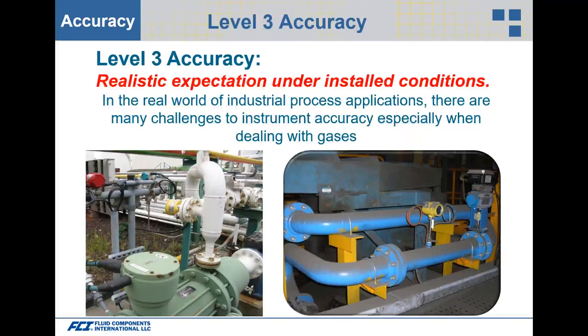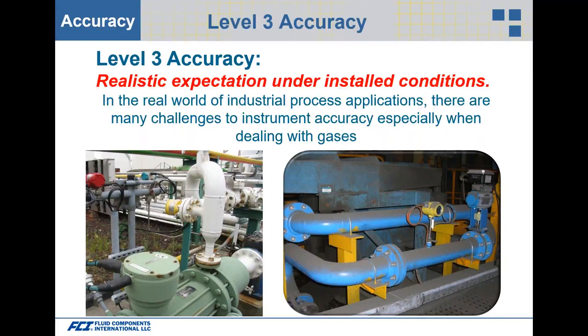Level three is the realistic expectation under installed conditions. When talking about air and gas applications — aeration basins, digest gas, flare gas, flue gas — we're typically talking larger line sizes, using a point measurement inside the pipe. In large line sizes, you don't have the luxury of lots of straight run to produce a good turbulent flow profile.